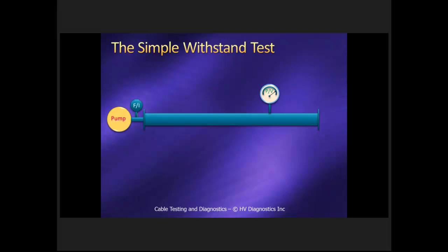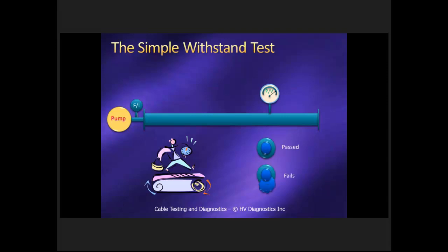For those who know the analogy, the pressure in the pipe is analogous to the voltage, and the flow is analogous to the current. When we do a simple withstand test, there are two outcomes. It either passes or the cable fails. If it fails, you get dielectric failure, and you have to find the fault. It tells you very clearly if you have a problem in the cable or not. There's not a whole lot of diagnostic value to it, but make no mistake, if the cable fails, that cable shouldn't have been in service in the first place, particularly under the voltages prescribed by the IEEE.